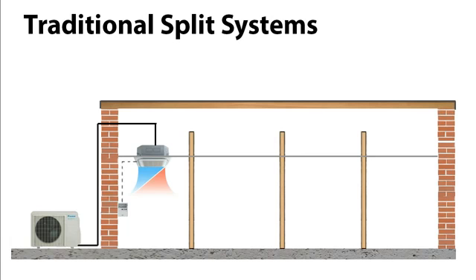So the reason VRF units were designed is because traditional split AC unit systems can only provide cooling to a single zone, and that zone can only be heated or cooled. As you can see on the screen here, we've got a building and we've got our outdoor condenser unit with our evaporator inside of the cassette, and this unit can only provide heating or cooling.